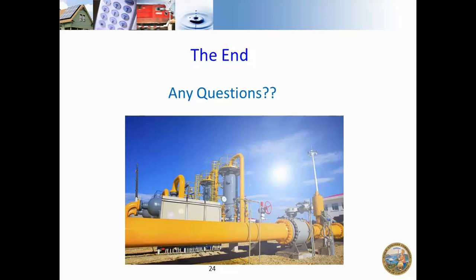If you have an older system, the only requirement you have to meet is the low pressure distribution system standard. A low pressure distribution system means whatever can be safely delivered to the customer — in this case, measured in ounces. As long as you don't go below what customers can use — typically four ounces or four inches of water column — you're fine. For newer systems the upper limit is two pounds, older systems about a pound and a half, so your MAOP would be whatever the maximum inlet of the appliances attached to your system are, typically about a pound and a half.